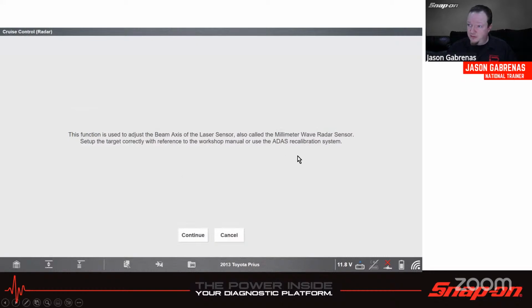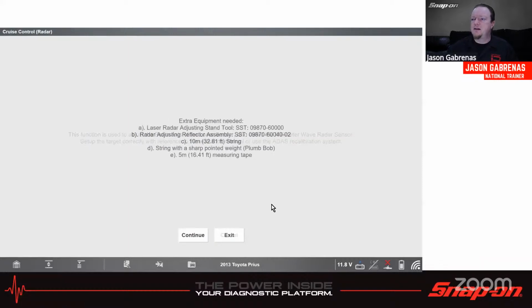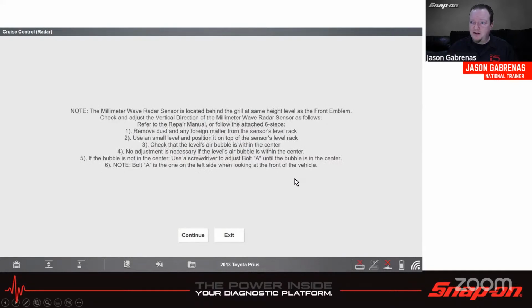Beam axis adjustment, same thing. For some reason, they call it a laser sensor, even though it's not laser. It's actually millimeter wave radar, same as all the other ones they use. They used to call it the laser sensor back in the day, and they've since changed that. So once again, you need the stand, the string, the plumb bob, measuring tape, all that good stuff.